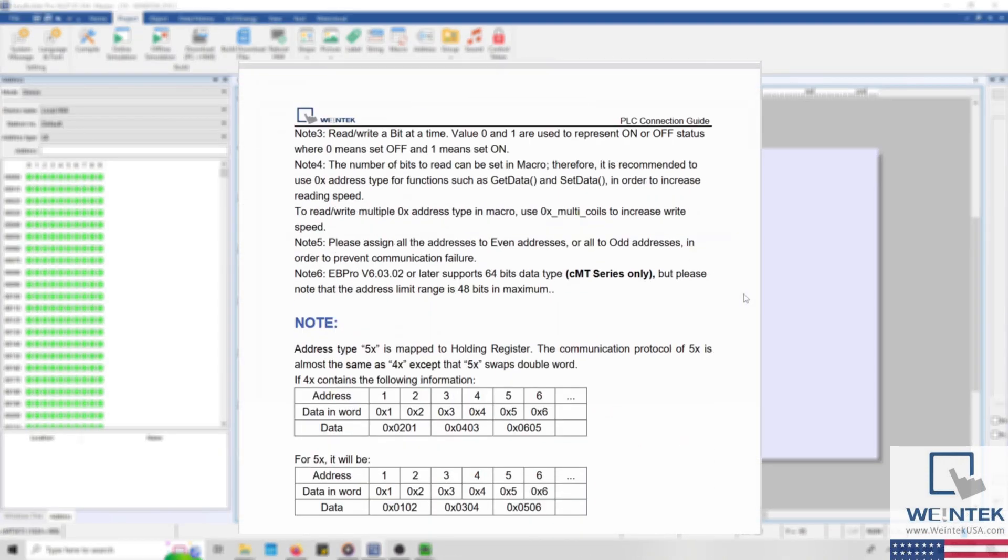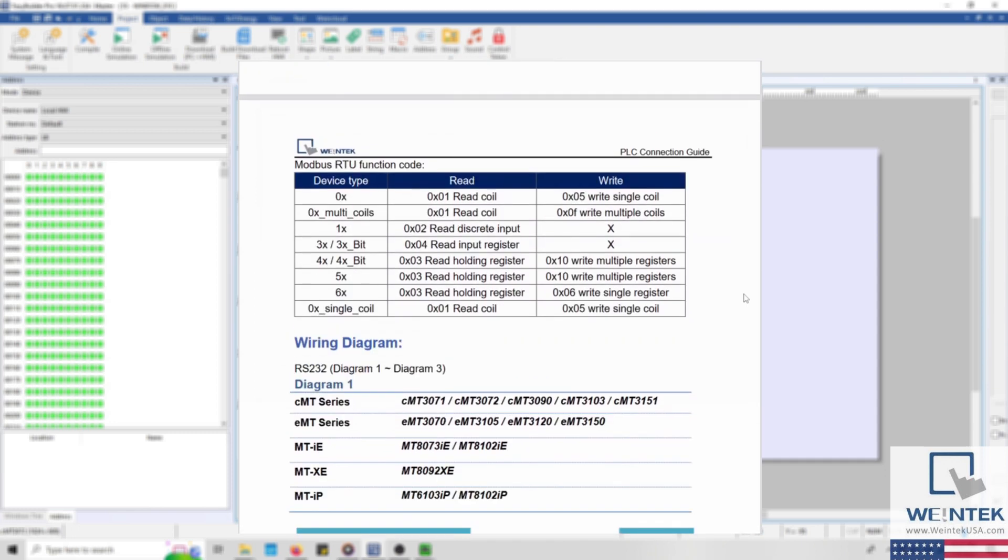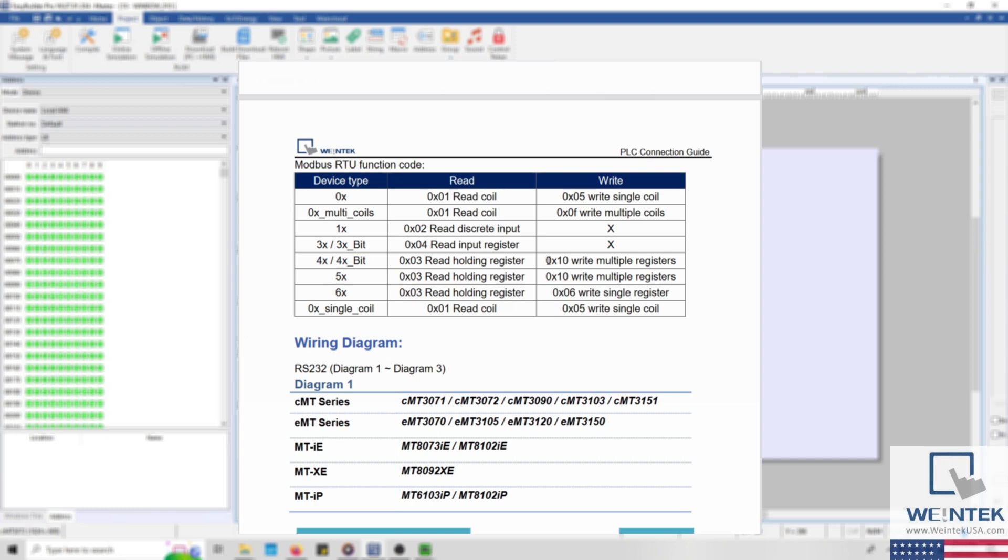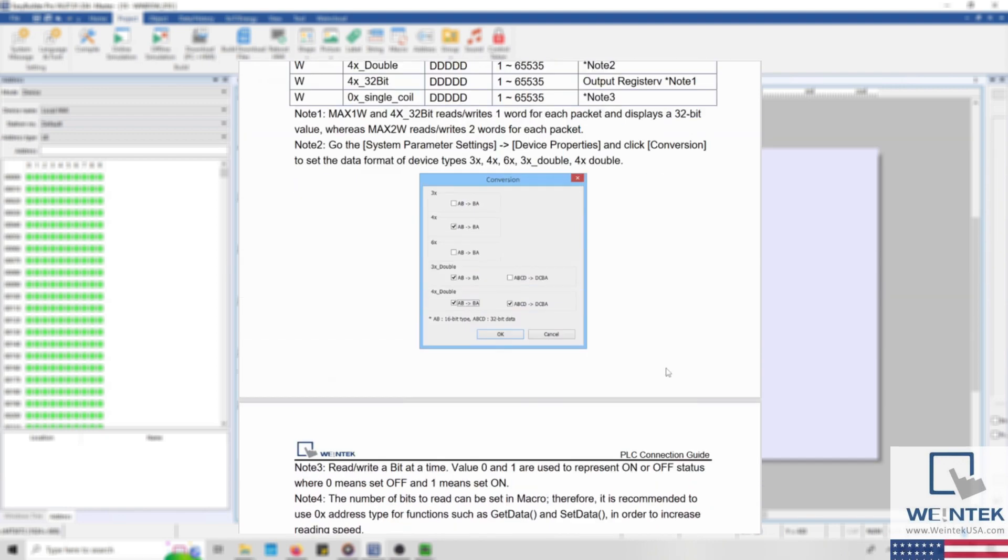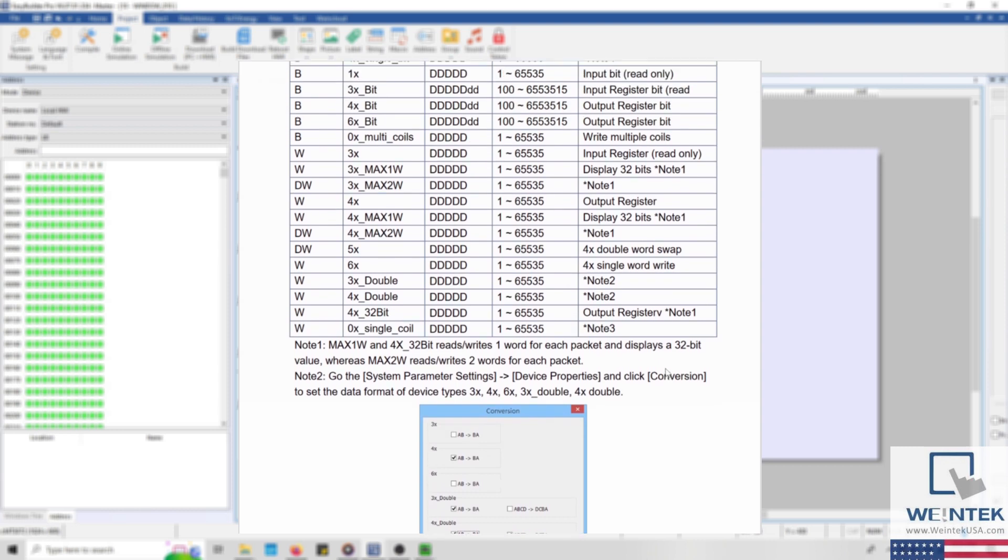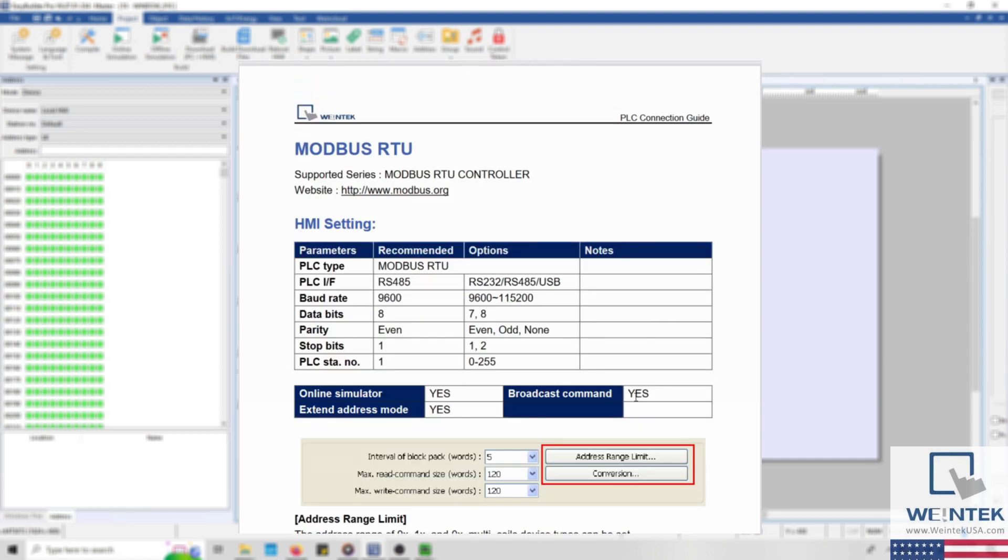It is also important to acknowledge that our Modbus RTU driver contains some additional Modbus addresses, each with a unique purpose. As an example, in most cases, when writing word data to a Modbus slave, you may use the 4x address type. However, a 4x address writes data using function code 16, which may not be supported on the external device. In cases such as this, it may be necessary to use a different address type. Other options include 6x, which writes data using function code 6. If the external device requires a word swap when reading 32-bit data, you may use the 5x address type, which supports this function. For a detailed list of each register and its corresponding function, please see the PLC connection guide for the Modbus driver that you are using within your application.